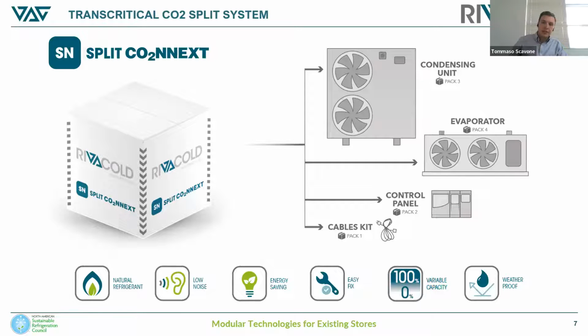The split system package includes the condensing unit, perfectly sized evaporator already fitted with probes and electronic expansion valve, the front room control panel, and also the cable kits that are provided for the power supply and the communication between condensing unit and evaporator. And we also offer these in different lengths that can be selected by the customer according to the specific installation requirements.